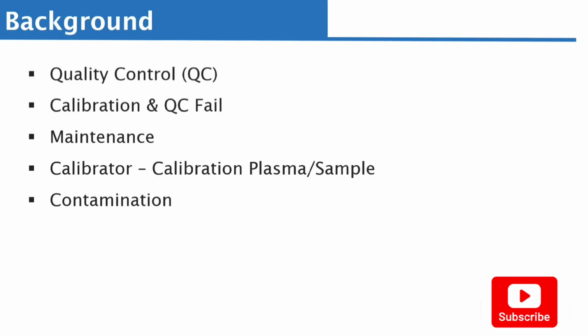So if you go for an interview and they say, how do you do maintenance? Or how do you do calibration? Or how do you do quality control? You just need to know they all follow the same principle. The only difference is you've got to let the analyzer know what you are doing, which I've already explained. That's why I gave you the background about quality control. So when you go for an interview and they say if your QC fails, what are you going to do? You consider doing calibration as part of what you are going to do. Now, that means that calibration is a way of ensuring that quality control is maintained. Therefore you can see calibration as a form of quality management system. And that is why, like I've said, we do calibration when a quality control sample fails.